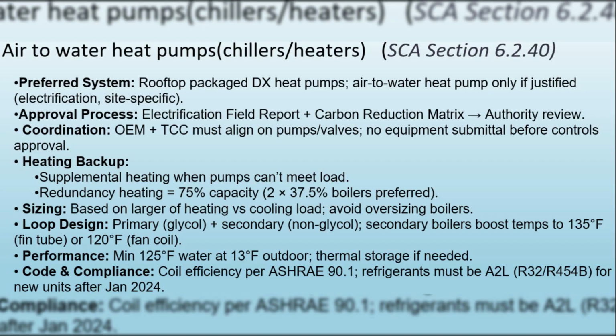This section explains when and how air-to-water heat pump chiller heaters can be used in school projects. The preferred option is rooftop packaged DX heat pumps, since they come factory assembled with refrigerant lines and full OEM controls. However, in some cases, air-to-water heat pump chiller heaters may be justified, for example, during building electrification retrofits or site-specific conditions. Designers must document justification in the electrification field report and submit equipment selections through the carbon reduction matrix for review. Air-to-water systems are more complex than packaged DX units. They require coordination between the chiller, heater manufacturer and the temperature controls contractor, especially for pumps and bypass valves. No equipment submittal should be approved before control submittals demonstrate this coordination.